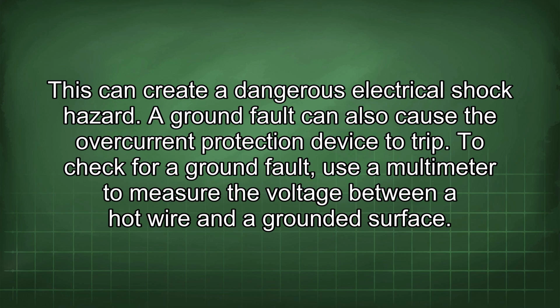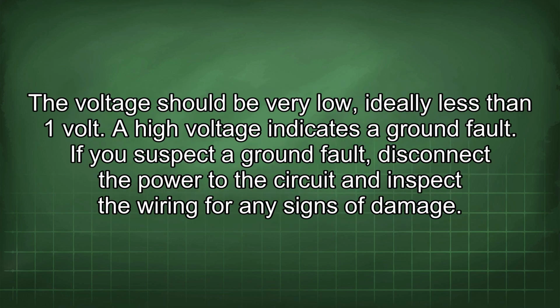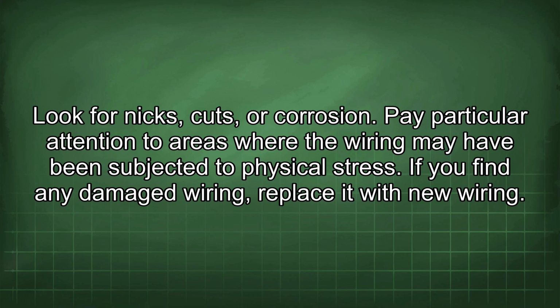To check for a ground fault, use a multimeter to measure the voltage between a hot wire and a grounded surface. The voltage should be very low, ideally less than 1 volt. A high voltage indicates a ground fault. If you suspect a ground fault, disconnect the power to the circuit and inspect the wiring for any signs of damage. Look for nicks, cuts, or corrosion.